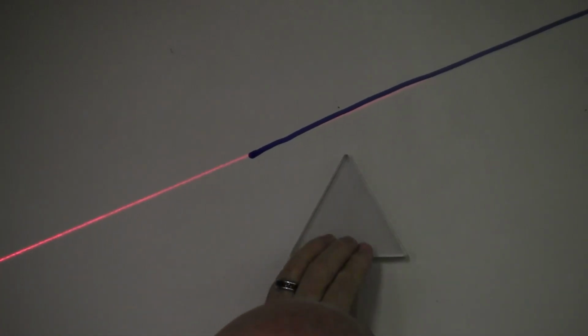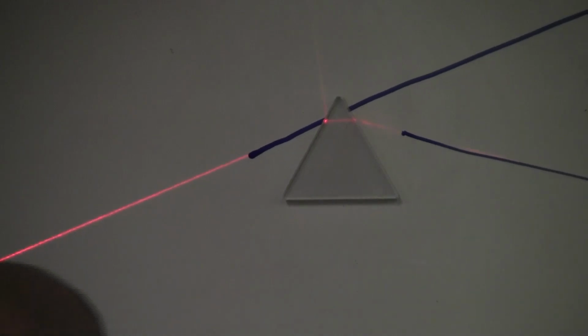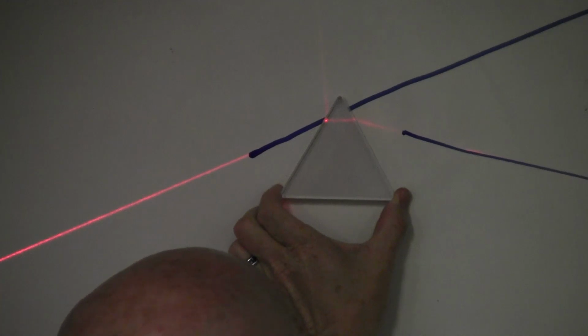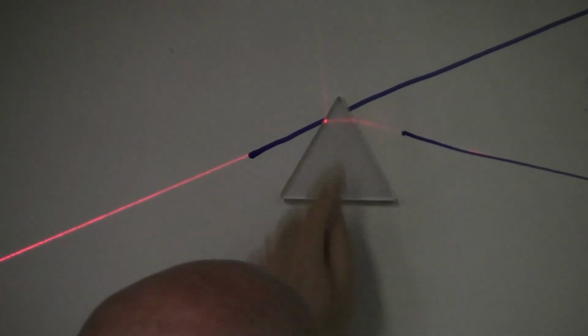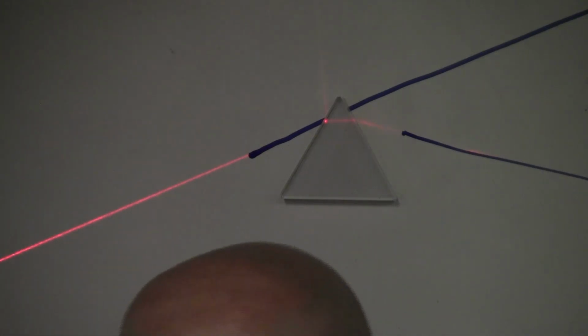And if I go ahead and put this right here, then this is where the light is going once the prism is put there. Now, there is some adjustment, and you'll see me do this with the equipment. You've got to get the prism adjusted just right so that the light going through the top of the prism is parallel to the base, but that's really easy to do with our equipment.